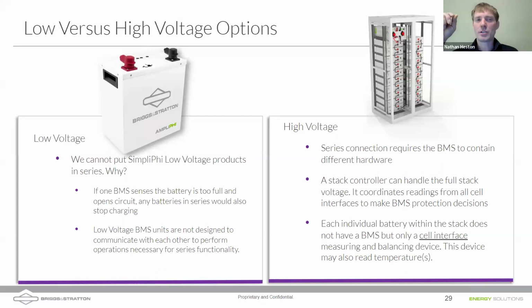There are two different questions here: how many cells have to go out internally within an individual battery module, versus knowing whether a whole battery module in a bank goes out, which depends on that specific battery. For instance, if this battery was non-functional in a system, you'd see it communicating outward that it's not discharging, or giving a warning like an over-temperature condition. I can't give a quantitative answer on how many cells inside a large battery pack have to fail - this battery probably has on the order of 200 cells, around 20 in parallel, 16 in series, so more than 200 cells total. I just don't know exactly how many have to go bad before something like that happens. That's the best I can do - I appreciate the question, please keep them coming.